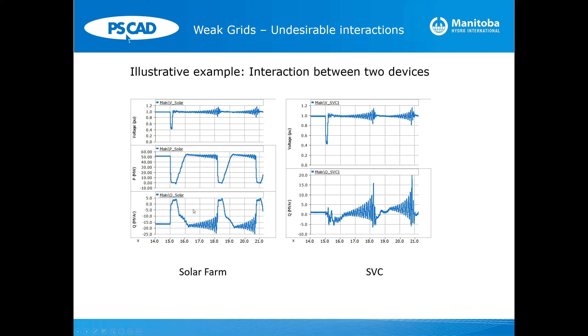I would like to spend a few minutes to discuss inverter operation under weak grid conditions. So there's a lot of words here, and the key point I'd like to address is the voltage, especially phase angle at weak grid locations. Inverters are extremely reliant upon measuring the voltage magnitude and angle at the point of connection. So maybe I can explain through an illustration rather than words. For the inverter to operate correctly, it relies heavily on a good measurement of your voltage phase angle.